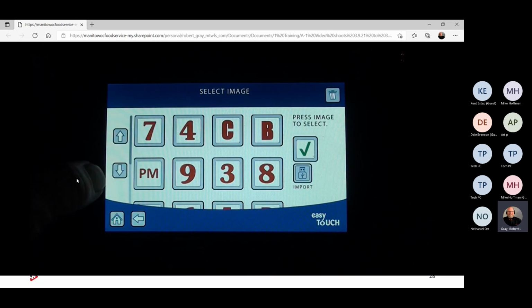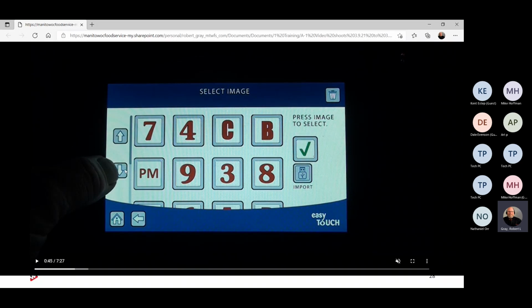Then the next thing you have to do is select an image. You can scroll up and down to find pre-programmed images, or you may import a JPEG from a USB stick. If you're going to import it, I would use a blank USB stick and put the image on that. This way the UI does not have to look through 100 files to find all the pictures. You're just going to do the one on the USB stick at a time. Put that in the USB port, hit import, and select the appropriate picture.